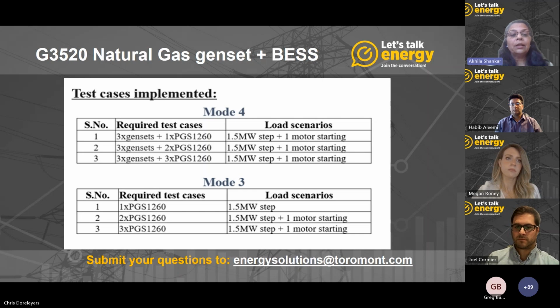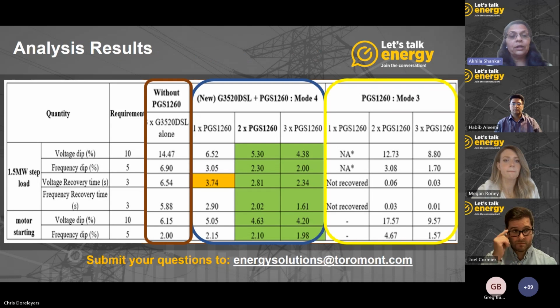And this was done with the combination of a single 1260 kilowatt battery energy storage system, and then with 2, and then with 3. And the results were recorded, which I'm going to show in my next slide. In the mode 3 test case, it was only the battery energy storage system that was subjected to the same set of loads, the 1.5 megawatt load in the first step and the motor starting in the second step. Now, if we can go to the next slide, we will see the results in more detail.